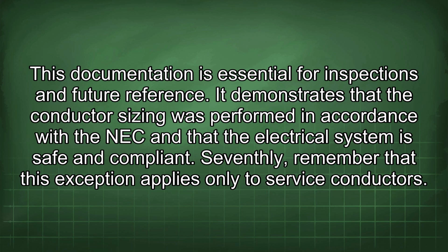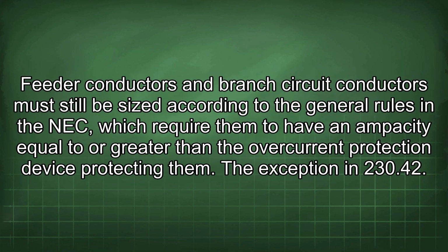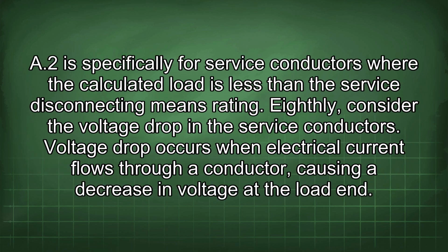It demonstrates that the conductor sizing was performed in accordance with the NEC and that the electrical system is safe and compliant. Seventhly, remember that this exception applies only to service conductors. Feeder conductors and branch circuit conductors must still be sized according to the general rules in the NEC, which require them to have an ampacity equal to or greater than the overcurrent protection device protecting them. The exception in 230.42(A)(2) is specifically for service conductors where the calculated load is less than the service disconnecting means rating.